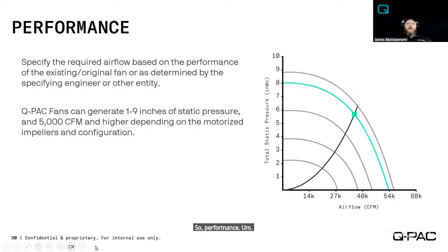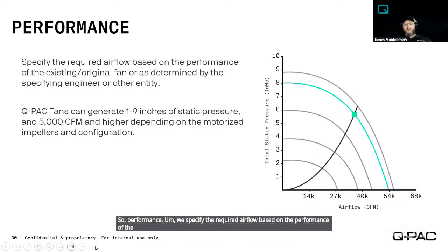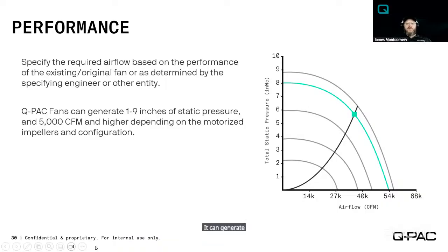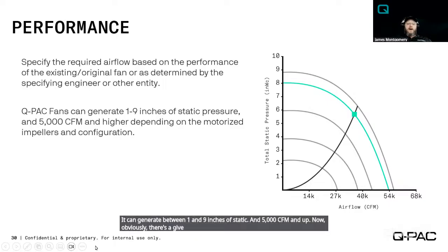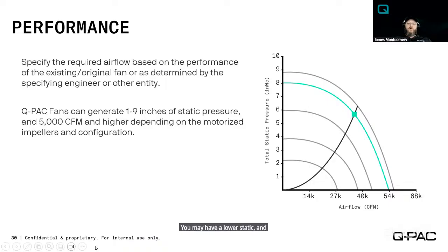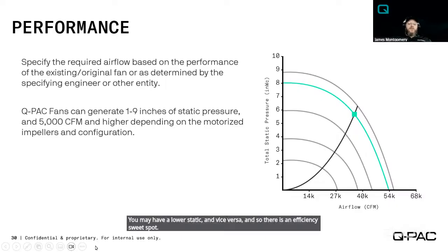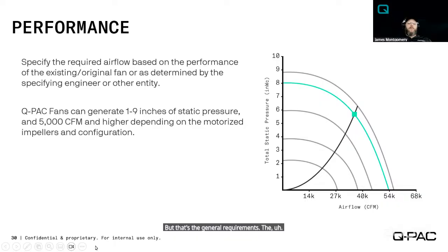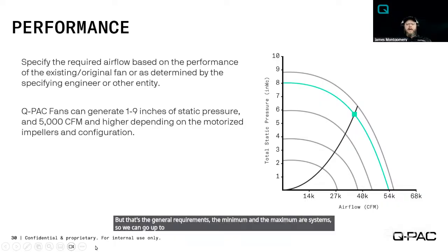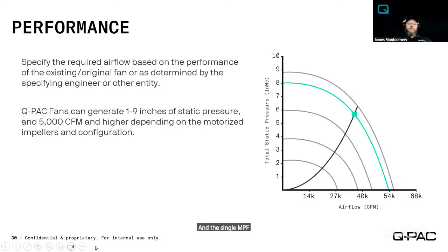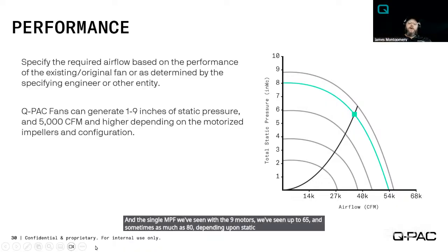We specify the required airflow based on the performance of the existing fan. And so when you provide us with those specifications, the Q-PAC system, the Q-PAC fan, can generate between 1 and 9 inches of static and 5,000 CFM and up. Now, obviously, there's a give and take there. If you've got a higher CFM, you may have a lower static, and vice versa. And so there is an efficiency sweet spot, but that's the general requirements, the minimum and the maximum of our system. So we can go up to 9 inches of static. And the single MPF we've seen with the 9 motors, we've seen up to 65 and sometimes as much as 80, depending upon static, 80,000 CFM with the single one.